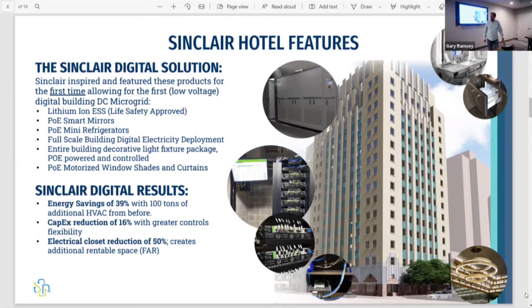So this gives me emergency backup for elevators, stairway pressurization fans. Yes sir, so do you size for 4 hours, 8 hours? 2 hours is code required, right, but with this battery I get 6.6 hours. The reason is I can only buy them in full cabinets, so if I needed 1 cabinet plus a little extra, I have to go to the next cabinet - you cannot buy partial, it's multiples of 166 kWh. But in future projects, I don't want it to be just the emergency backup power.